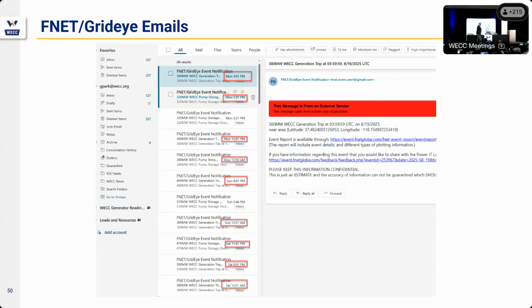So there's a trigger limit on these, about 300 to 400 megawatts in the West. It takes a resource deficiency, loss of generation, or an increase of load of at least 300 megawatts for this FNet to trigger. We generally get a couple a week, maybe 5 a week, maybe 10 a week — not 12 a day.